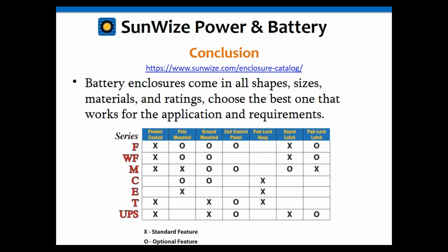So in conclusion, battery enclosures come in all different shapes, sizes, and material ratings. The best one for your application depends on requirements like location, whether it needs to be indoor or outdoor, and the size of the batteries being put in it. Smaller batteries can go on a pole or wall; bigger batteries probably need to be on the ground. Front opening versus top opening is just a preference. And whether you install the electronics in the battery enclosure or in a separate enclosure just depends on what's preferred. Generally we try to install the electronics with the batteries.